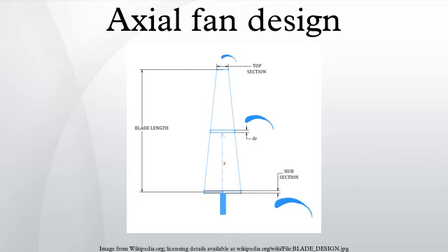Also, the blades are made very long with varying blade sections along the radius. Calculation of parameters: since the calculation cannot be done using the inlet and outlet velocity triangles, which is not the case in other turbomachines, calculation is done by considering a mean velocity triangle for flow only through an infinitesimal blade element. The blade is divided into many small elements and various parameters are determined separately for each element. There are two theories that solve the parameters for axial fans: slipstream theory and blade element theory.